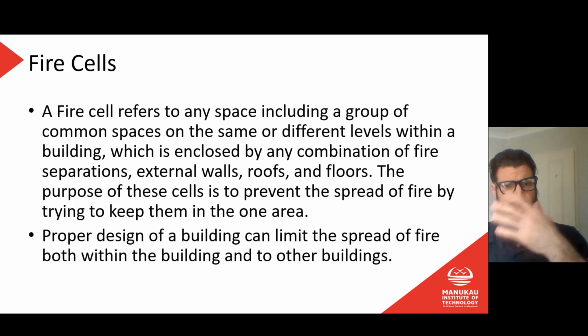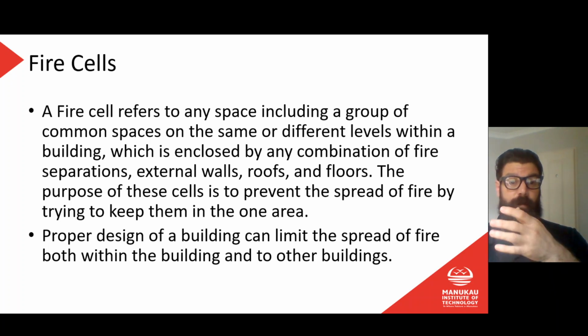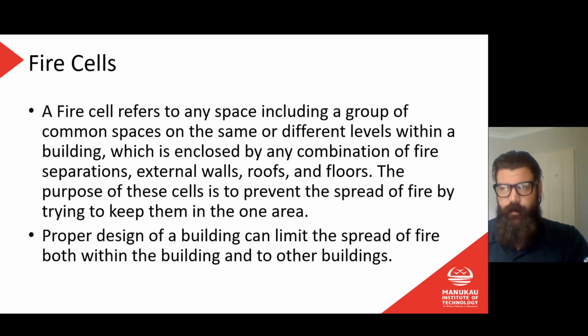We all want to run services through buildings. And if you put a hole in a firewall, what you're doing is compromising that fire cell. So you're creating a point at which fire may be able to spread and get through that wall or through that fire cell. So that creates a real hazard. So that was always a big deal in the fire industry, that when we went and did the annual inspection of the fire cells or fire separations, if it's a big enough building where people are coming in and out all the time, you'll always find new holes, fresh holes in your fire cells.